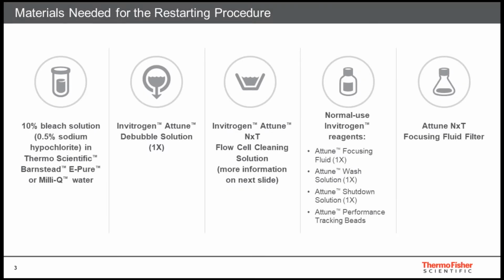Materials we will be using during the startup procedure are 10% bleach solution, which is 0.5% sodium hypochlorite, in the cleanest possible available water, Attune debubble solution, Attune NxT flow cell cleaning solution that we'll discuss further in detail in the coming slides, normal use Invitrogen reagents, which include focusing fluid, wash solution, shutdown solution, and the Attune performance tracking beads that will be used to QC the instrument. Lastly, we will require 2 new Attune NxT focusing fluid filters.